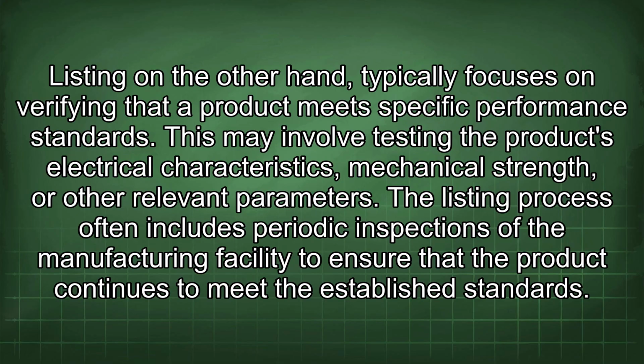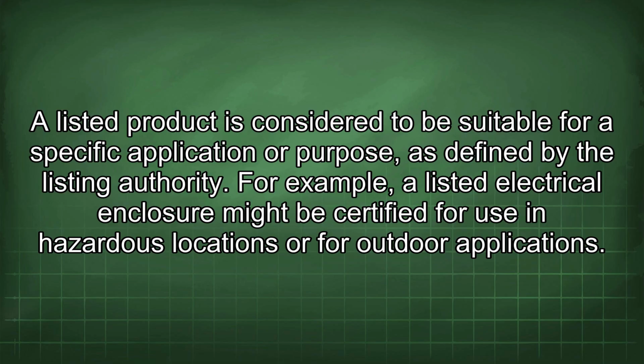The listing process often includes periodic inspections of the manufacturing facility to ensure that the product continues to meet the established standards. A listed product is considered to be suitable for a specific application or purpose, as defined by the listing authority. For example, a listed electrical enclosure might be certified for use in hazardous locations or for outdoor applications.